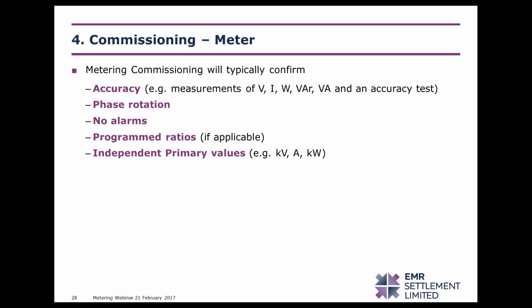Looking firstly at the commissioning of the meter. The purpose of the commissioning of the meter is to prove that the meter is operating accurately and correctly. Typically, it will confirm accuracy through measurements of voltages, currents, power, and an accuracy test against an independent energy standard used for comparison. It should confirm that the phase rotation is correct. At the time of commissioning, no alarms were present, for example, a voltage phase failure alarm. It should confirm that the programmed ratios are correct, if these are applicable to the meter.